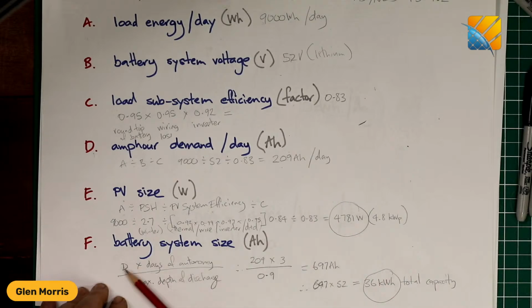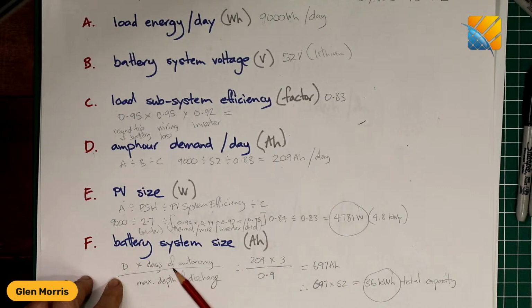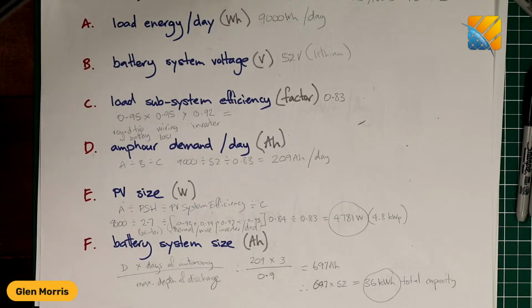And battery system sizing really is all about how many days of no input from renewable sources, what we call days of autonomy, just running off your battery. Now, in 4509 Part 2, it's assumed that a day of autonomy is a total eclipse, absolutely no input, but we know there's always a bit. So it's really a worst case scenario. So how many days of total eclipse can your system run for? The recommendation in 4509 Part 2 is, if no auto start generator is available, 5 days of autonomy. If there is an auto start generator available, a minimum of 2 days of autonomy. Now, those are not rules, they're just recommendations. So let's say somewhere between 2 and 5 days would be a good range to look at.